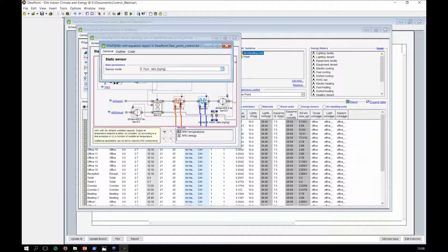You can log mass flow, temperature, CO2, relative humidity. In this scenario, my interest is logging absolute humidity ratio, so kilograms of water per kilogram of dry air. I put it on the return air side because the return air is the most representative of what's happening inside the building.